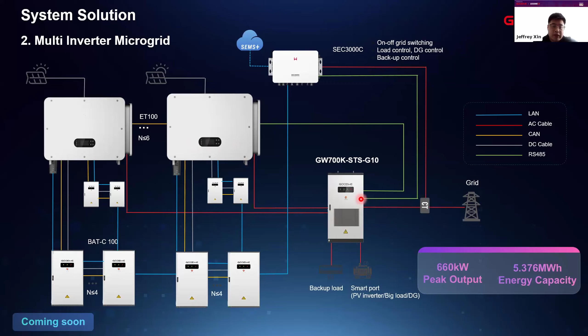This is used more in Southeast Asia, especially Malaysia and Thailand, because they've already installed on-grid inverters, not only GoodWe but other brands too. After a few years, if they want to add a battery, you can't directly add a battery to an on-grid inverter — you need a PCS together with the battery. The PCS gets power from the AC side, from the generation of the on-grid inverter, converts it from AC to DC, and charges the battery, since the battery needs DC current.